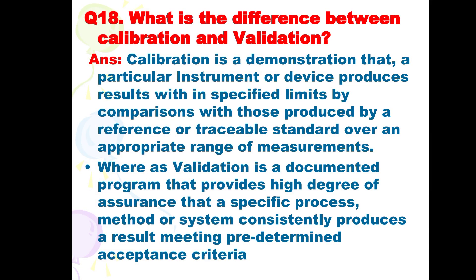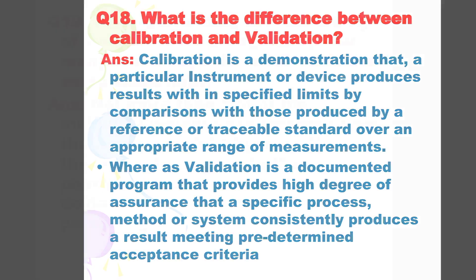Next is: what is the difference between calibration and validation? Calibration is a demonstration that a particular instrument or device produces results within a specified limit by comparison with those produced by a reference or traceable standard over an appropriate range of measurements. Whereas, validation is a documented program that provides a high degree of assurance that a specific process, method, or system consistently produces a result meeting predetermined acceptance criteria.